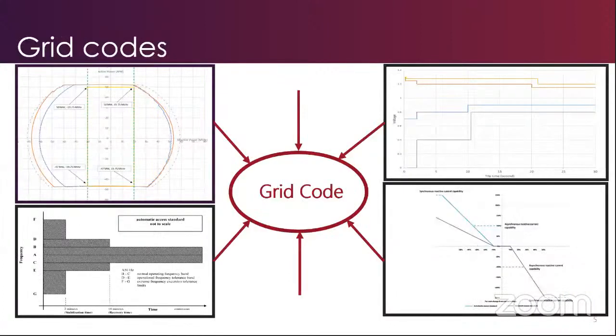To start with, I thought of starting with the grid codes. As per my experience, grid code is a key part of renewable connection as well, like in any other connection. It sets the technical requirements for a generator connection. The idea is that when you're connecting a generator, it can meet this grid code. The grid codes are typically developed by considering the operating envelope of that power system, meaning if a generator can meet this grid code, the operator can comfortably operate the system stably and reliably.